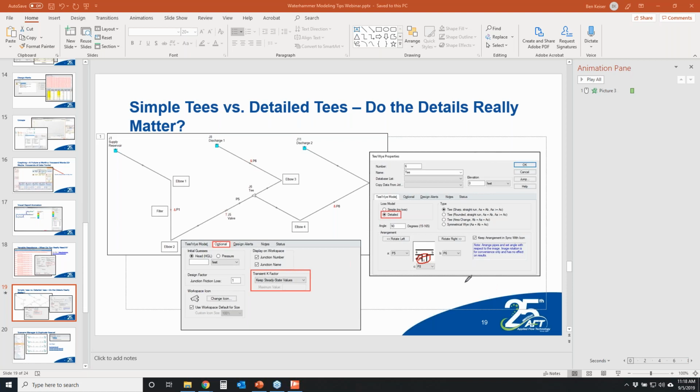And as your flow distribution through your Waterhammer event is changing, your potential correlations for your detailed T calculations could also be changing. And so the changes in correlations that it would be switching could potentially cause mathematical anomalies that may not be realistic. So if you're going to use detailed T's, A, be sure that you have all of this information defined exactly correct.